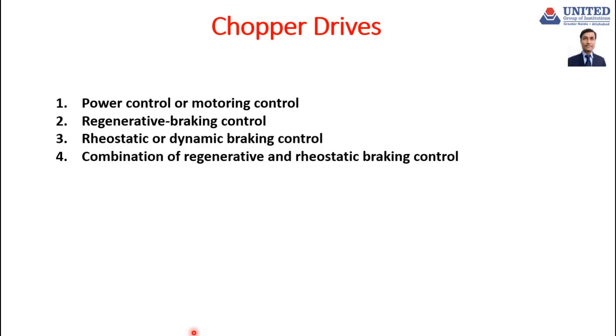During the regenerative braking operation, motor voltage must be greater than input voltage. If the input voltage is non-receptive during regenerative braking, then motor voltage will be less than input voltage, and in that case regenerative braking may not be possible. In that case, rheostatic braking or dynamic braking is possible for DC drives. DC choppers are mostly used in battery operated electric vehicles, etc.